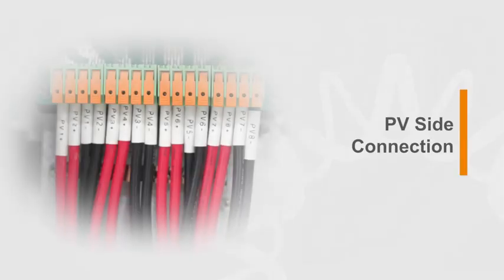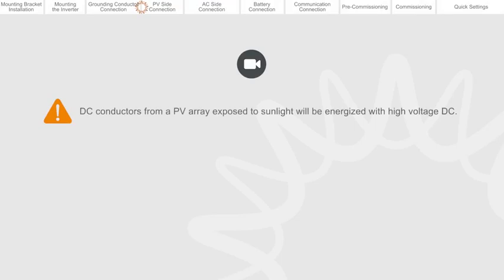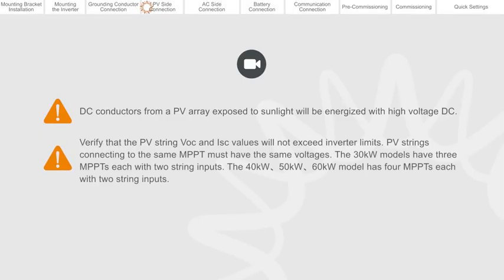PV side connection. DC conductors from a PV array exposed to sunlight will be energized with high voltage DC. Verify that the PV string VOC and ISC values will not exceed inverter limits. PV strings connecting to the same MPPT must have the same voltages.